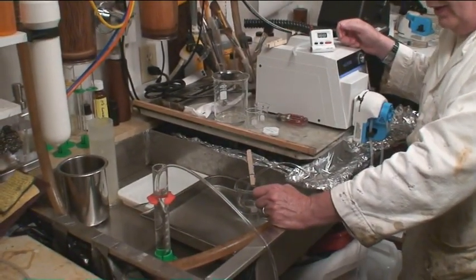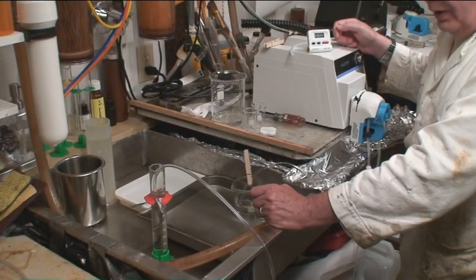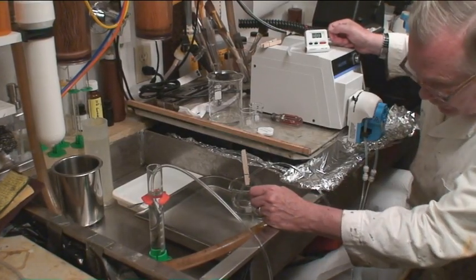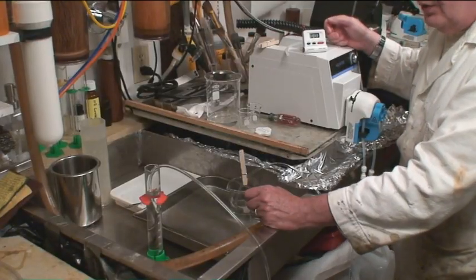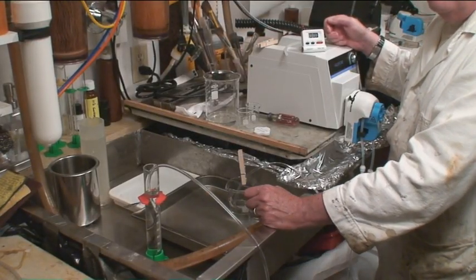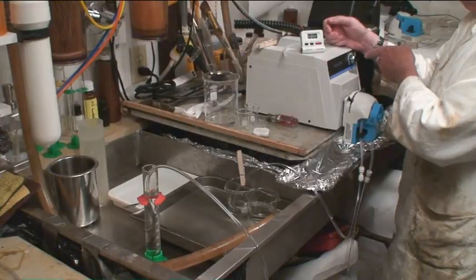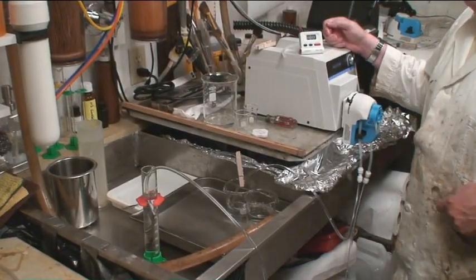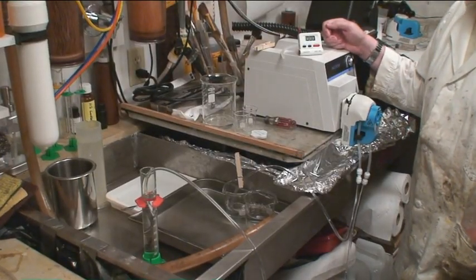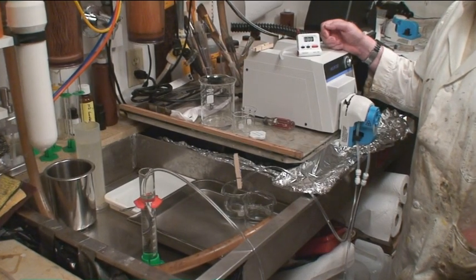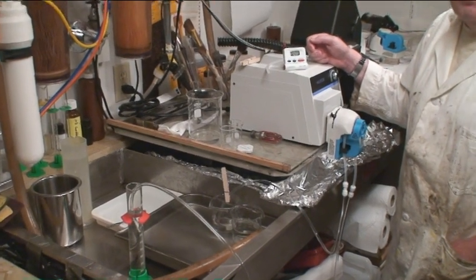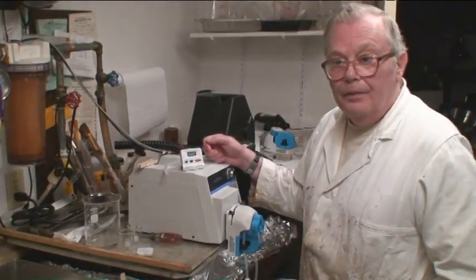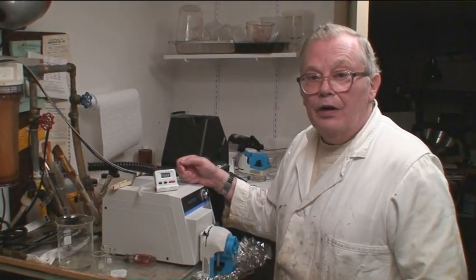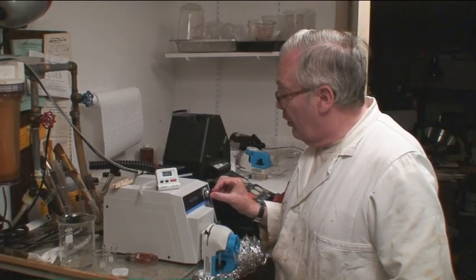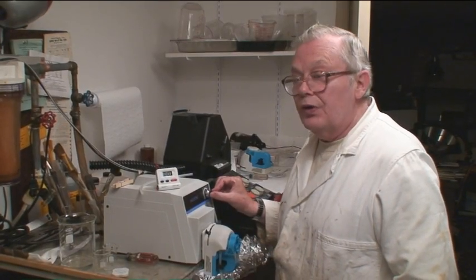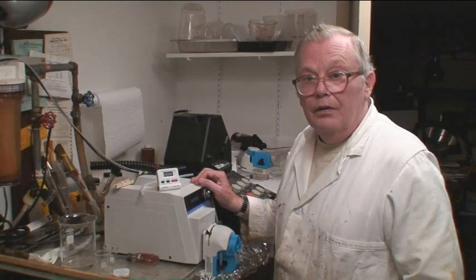So at a setting of 1, it delivered 40 milliliters, I believe. And at a setting of 2, it delivered 100. And you can go to finer gradients in between with the vernier knob, and with that you can construct a complete calibration curve of your pump with this type of tubing. After you're done with that, using the vernier knob on the potentiometer, you can select any flow rate that you wish.